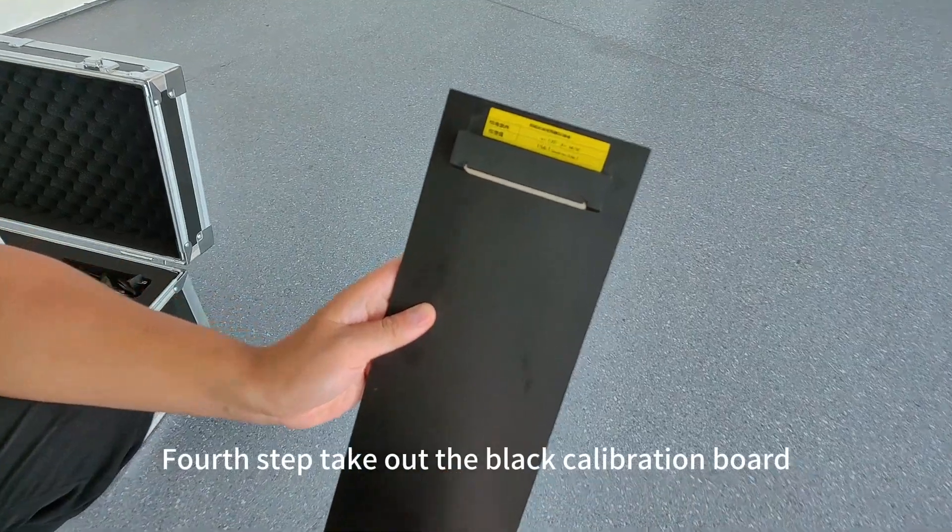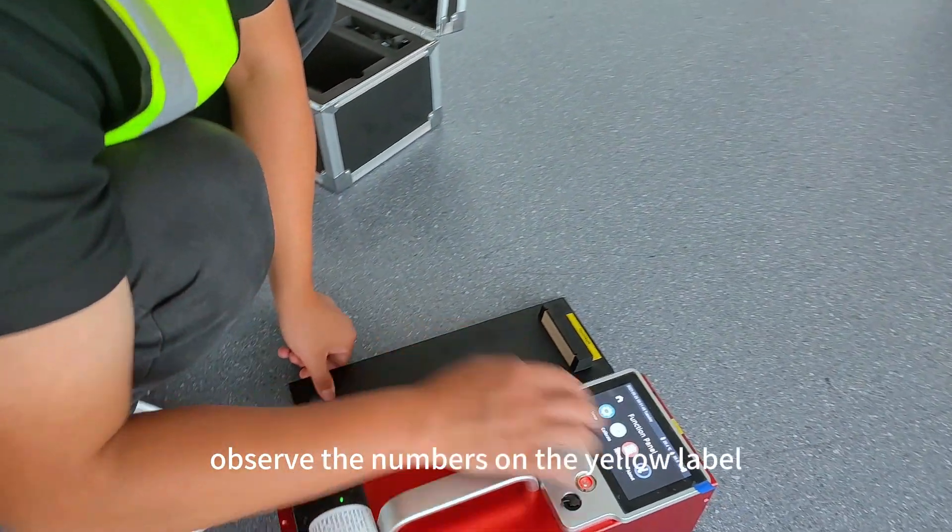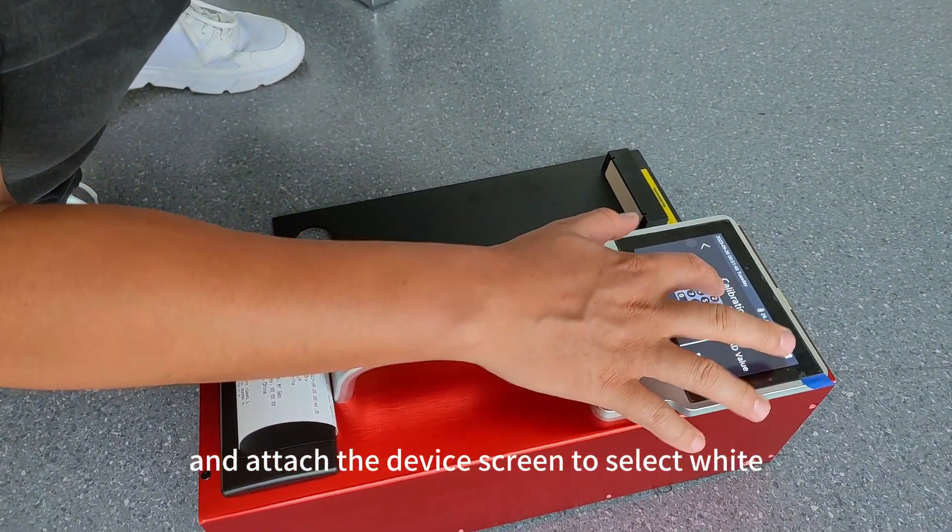Fourth step, take out the black calibration board, observe the numbers on the yellow label, and touch the device screen to select white.